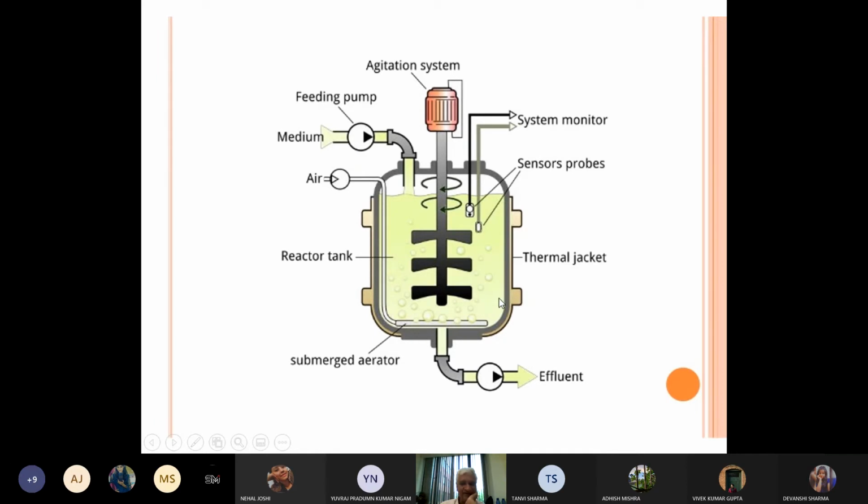So what I do first is, we will heat the media from outside to 100 degree, and then we put a steam. We definitely put a steam because under no circumstances you can raise the temperature to 121 degree by just thermal jacket. Correct? So I'm just telling you one more aspect of sterilization of media, and that is by steam. But think, what will happen if we directly put steam?